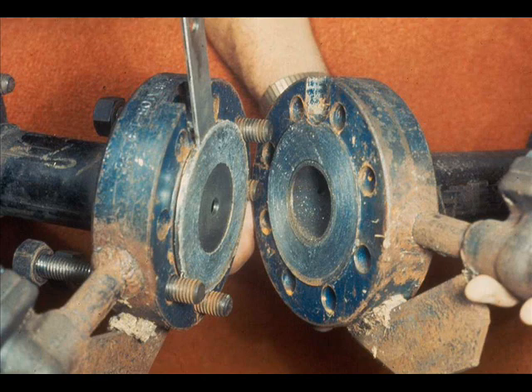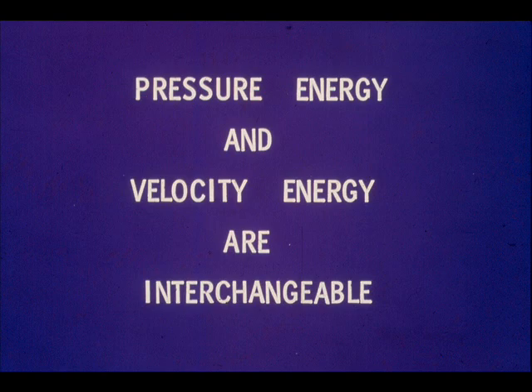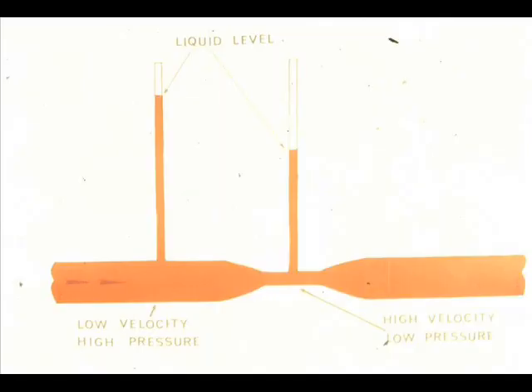The higher the pressure drop, the larger the flow. It is the pressure drop, or delta P, that is actually measured, but the flow can then be calculated. Since the orifice opening is smaller than the pipe, the velocity through the orifice is higher. In the module on fluid flow, we talked about pressure energy and velocity energy as being interchangeable. A Venturi tube can be used to show this interchange: velocity is highest through the smallest part of the tube, and at this point the pressure is lowest. An increase in velocity energy results in a decrease in pressure energy.